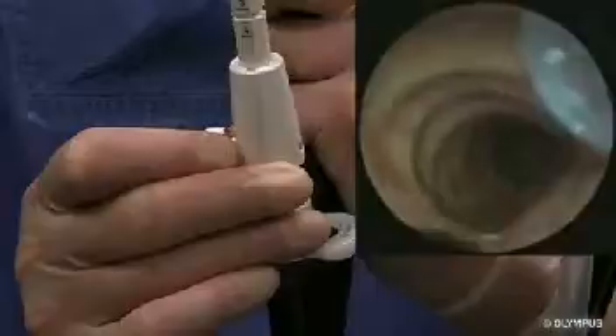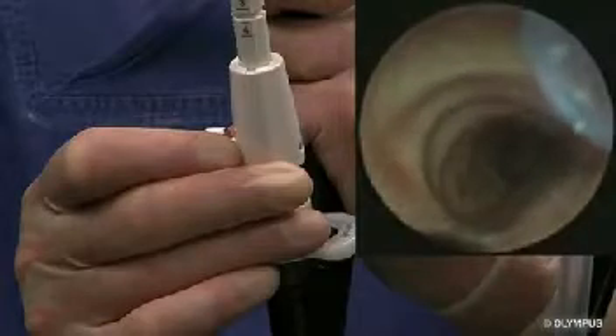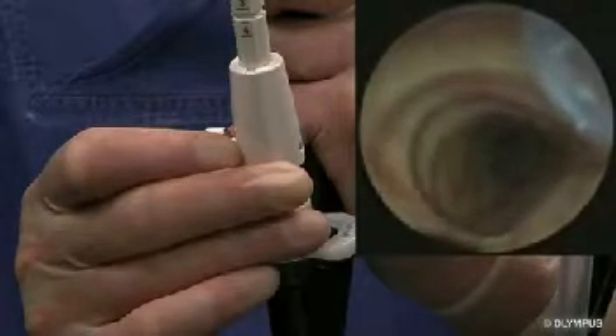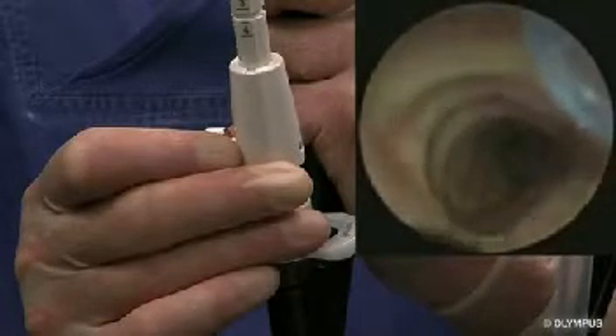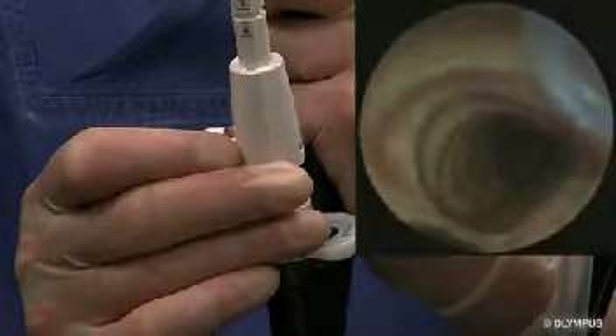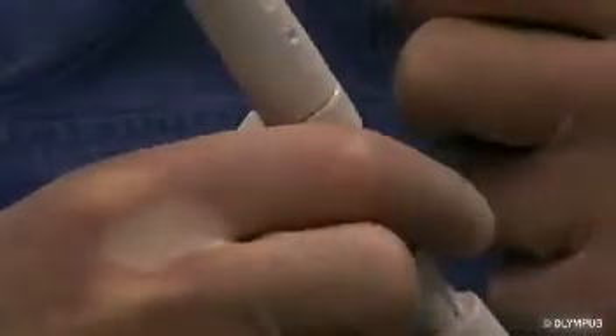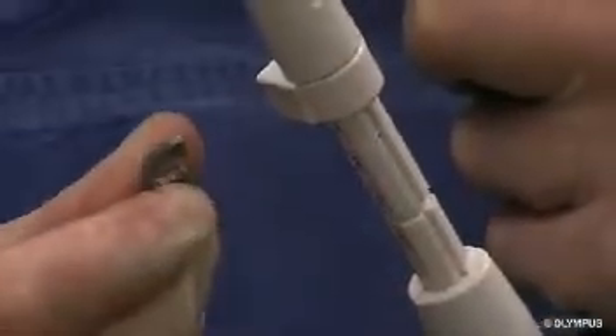Before activating the needle, confirm that the needle sheath can be seen in the endoscopic image. If in doubt, readjust the needle sheath. The next steps concentrate on needle activation. Check the distance to the targeted lesion and decide on required needle length. Remove the grey stopper, should a needle length larger than 2 cm be required. Push the needle adjuster lever. Fix the needle adjuster by locking the lever at a chosen position on the scale, or let the needle adjuster slide down the scale.